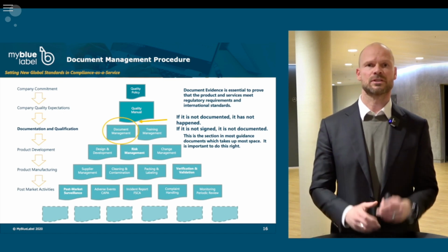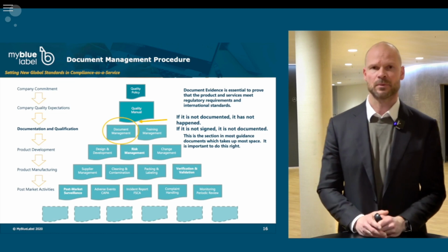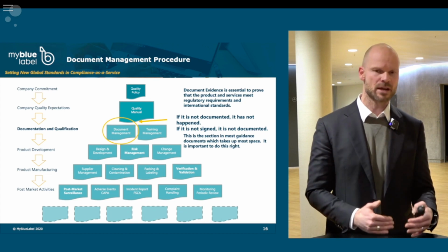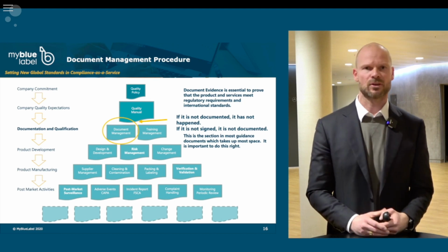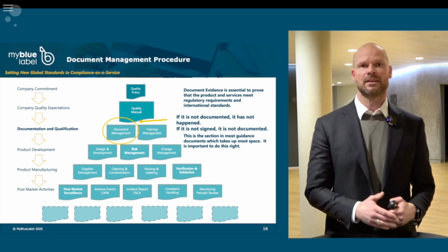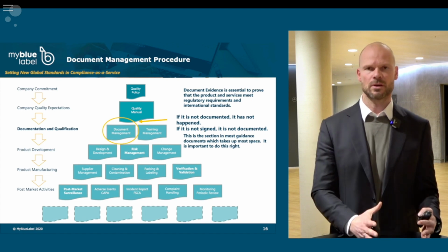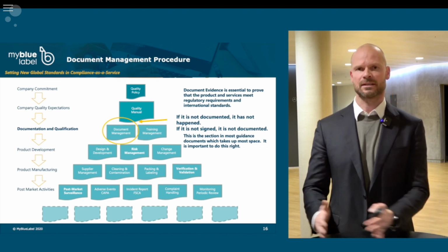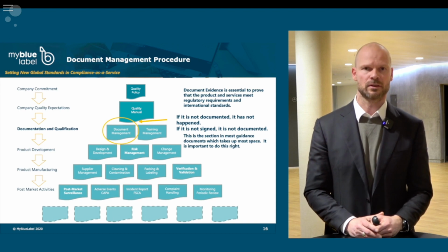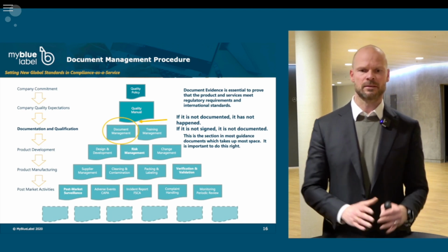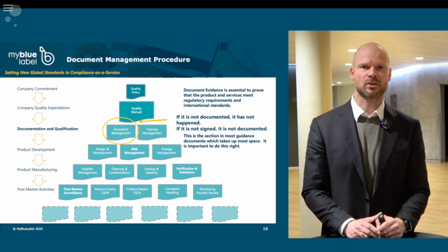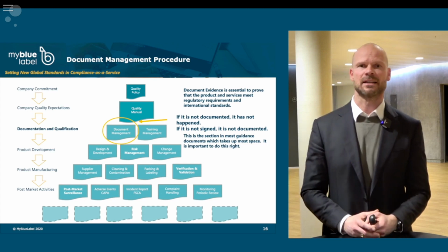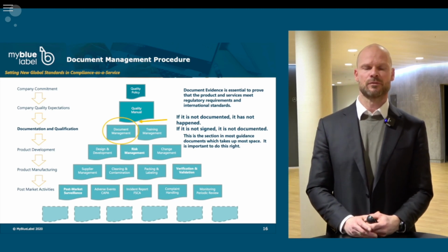So these two rules are something that you need to really keep in your mind, because it could be that you're working in a draft document, and you're very happy about the content, but if it's not signed, then it has never happened. So you need to make sure that you document your activities, and then you follow that activity until you have the result that you want. It's really important. And the date and timestamp of these documents is really important for the sequence of events that follows the whole design, development and production of your medical device.